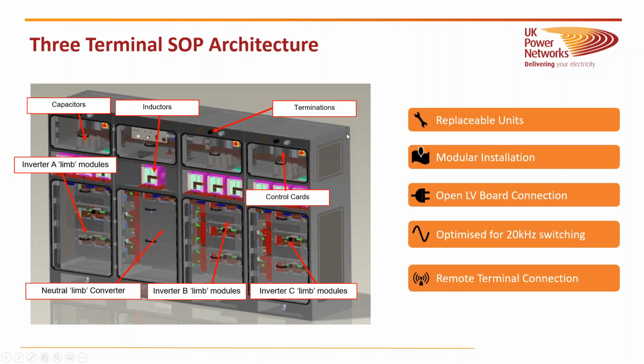So if I go to the next slide, this is the 3T SOP now, very similar in design, and it has all the same modular components as the 2T SOP, which makes the build very easy. So you've got the inverters A, B, and C. Now this is a 3-terminal SOP, so it connects to 3 feeders. You've got the neutral again, the bus bar behind it, and control cards for each one. So again, all replaceable units.